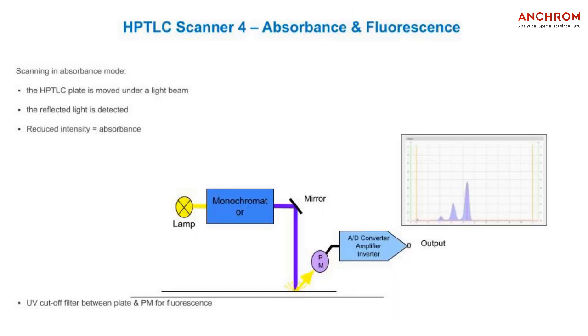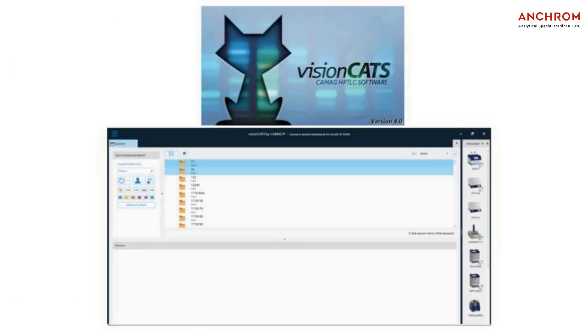The TLC Scanner 4 is a scanning densitometer. It measures the reflection of separated compounds in absorption or fluorescence mode. It is controlled by visionCATS software and enables quantitative evaluation of the generated densitometric data.